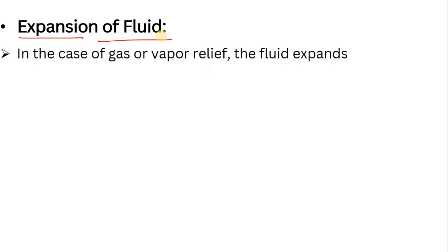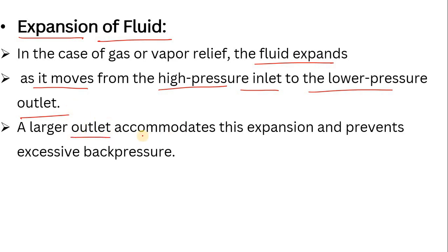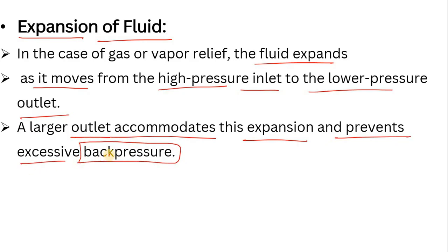The first reason is expansion of fluid. When your system becomes over-pressurized, in the case of gas or vapor relief, the fluid expands. When the fluid expands, the density decreases. The fluid moves from higher pressure at the inlet to lower pressure at the outlet, and a larger outlet size accommodates this expansion and prevents excessive back pressure. If this excessive back pressure is present, the PSV may not open or work properly. That's why a larger outlet size is recommended.